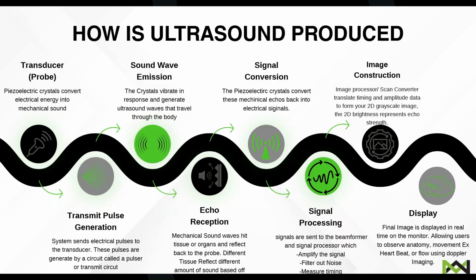Once this signal is processed, it then goes to image reconstruction. The scan converter translates timing and amplitude data to form your 2D grayscale image. The brightness is represented by the strength of echoes that are reflected back to the crystal. Finally, you have the image displayed in real time on the system monitor, allowing users to observe anatomy, movement, heartbeat, and flow.